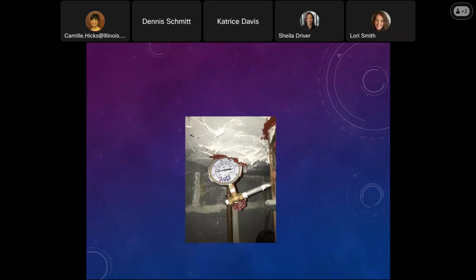We see gauges all the time on sprinkler systems. This is a sprinkler system gauge, which is not a problem. However, this gauge was last checked and they wrote it on the surface, 2013. But this photo was taken in 2019, and gauges need to be updated or replaced every 5 years. So it was non-compliant for that.